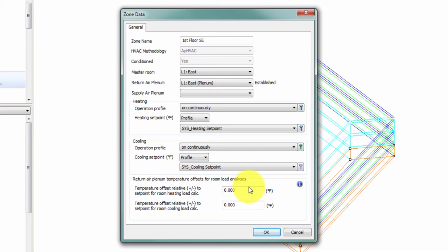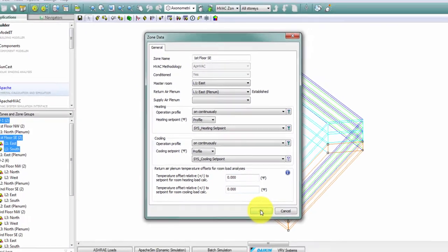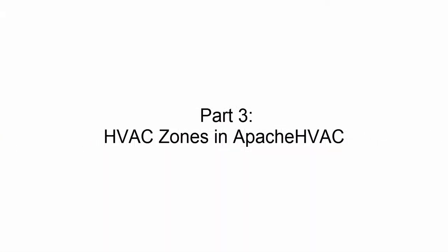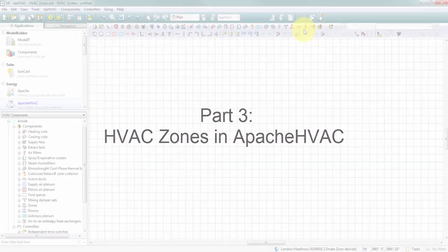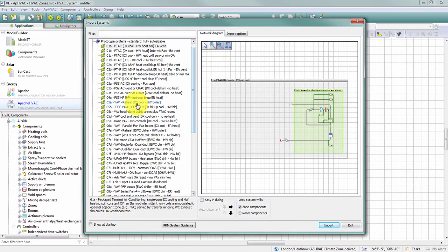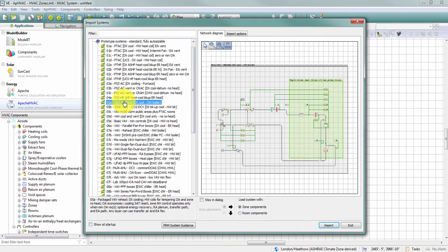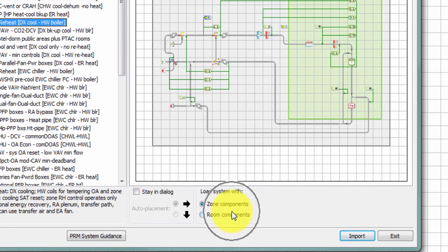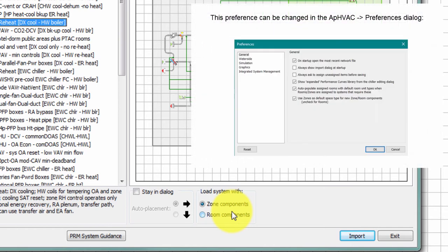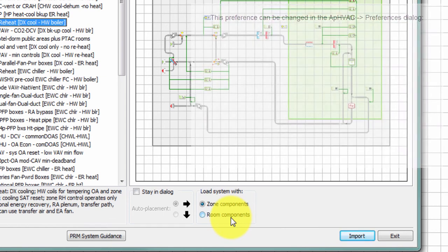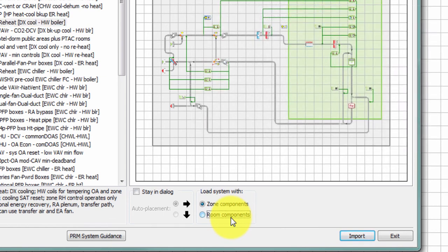As you might expect, these HVAC zones and zone groups give me some new options within Apache HVAC. I'll start by importing a prototype system from the library, just grab a 5A as an example, and you'll notice I have an option to load the system with zone components or room components. By default, the software has a preference for zone components, but if you'd like to work without HVAC zones like you would have been doing prior to VE 2017, you can always toggle to room components and continue to assign rooms to your systems without using HVAC zones.